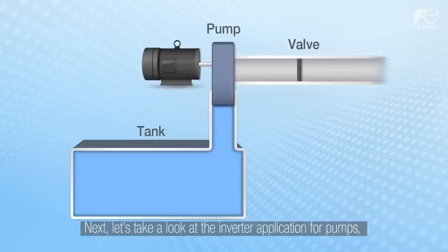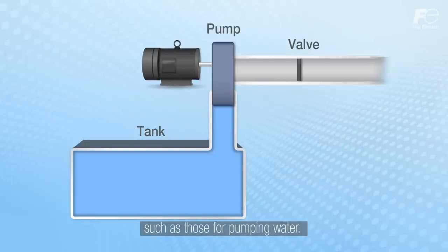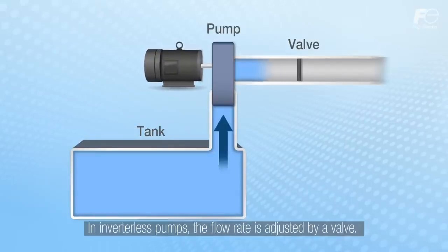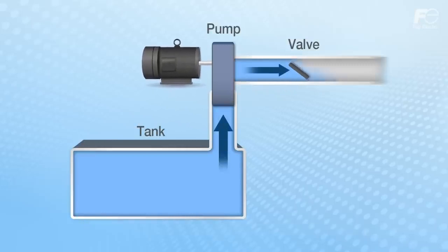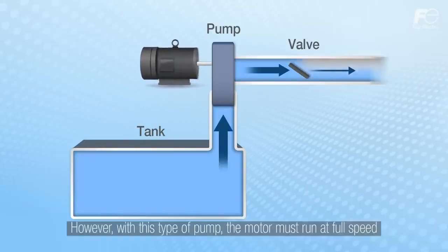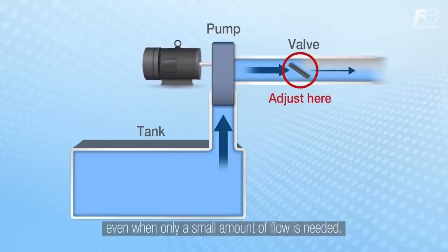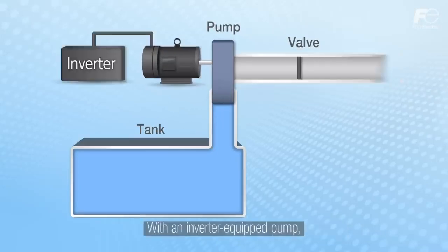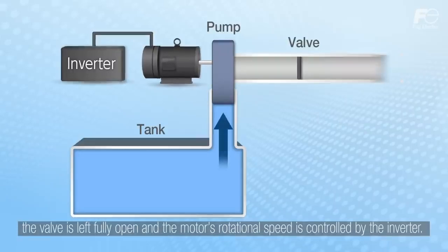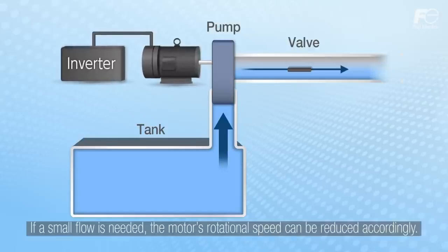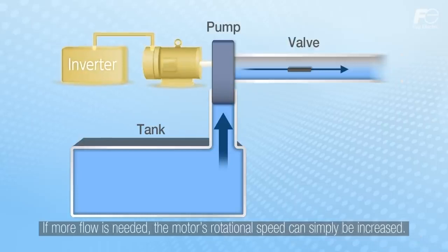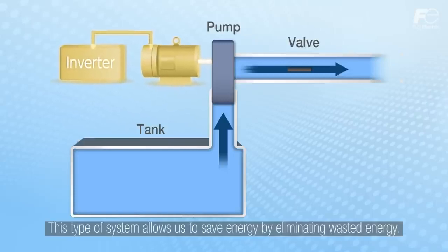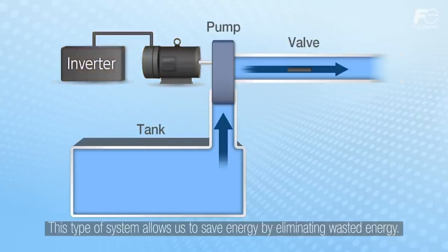Next, let's take a look at the inverter application for pumps, such as those for pumping water. In inverterless pumps, the flow rate is adjusted by a valve. However, with this type of pump, the motor must run at full speed even when only a small amount of flow is needed. With an inverter-equipped pump, the valve is left fully open and the motor's rotational speed is controlled by the inverter. If a small flow is needed, the motor's rotational speed can be reduced accordingly. If more flow is needed, the motor's rotational speed can simply be increased. This type of system allows us to save energy by eliminating wasted energy.